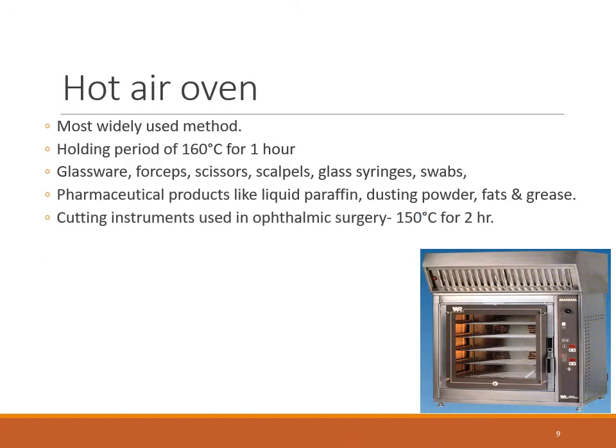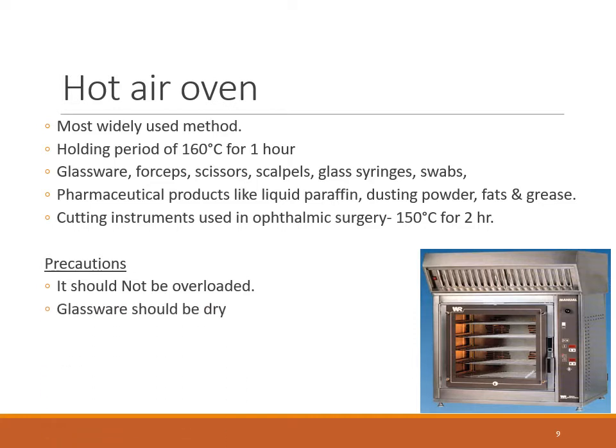For cutting instruments, we can use this hot air oven at 150 degrees Celsius for 2 hours. We have to take some precautions while handling the hot air oven. First, it should not be overloaded because the air has to pass between the objects. Glassware should be dry and it must be allowed to cool before the door is opened.